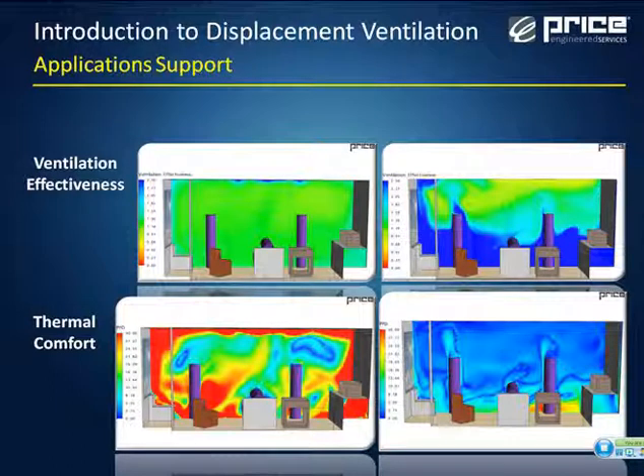If we take a look at the thermal comfort printout here, you can see that high velocity ceiling diffuser is throwing air across the ceiling. In some cases it's extending down the wall with significant velocity, and then down along the floor actually. So the red is showing 30% PPD, which is a measurement of draft. So this is 30% of people predicted to be dissatisfied in that red region. So that's extending all the way up around this one person.